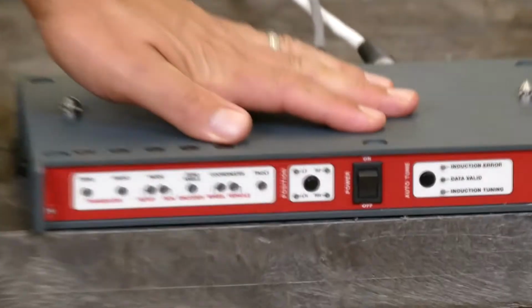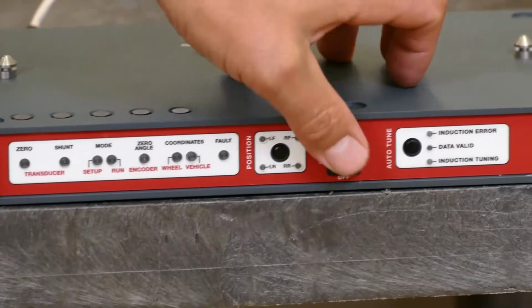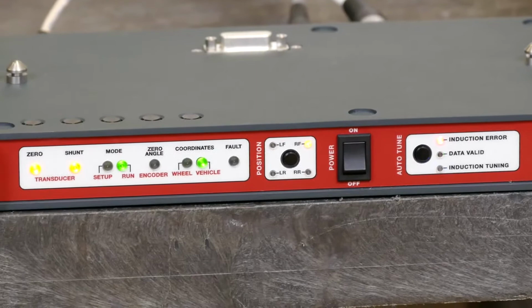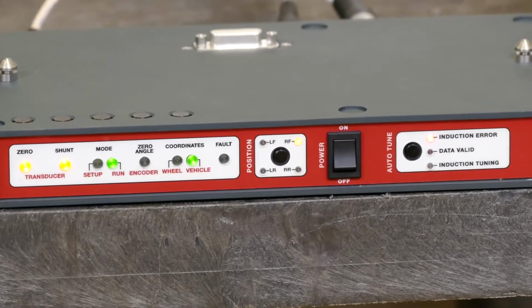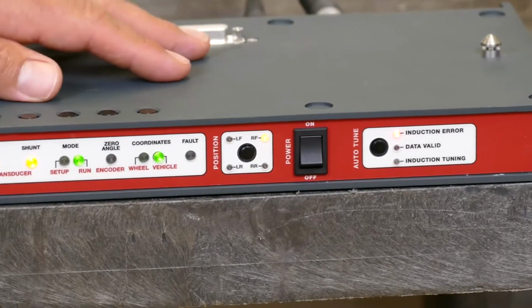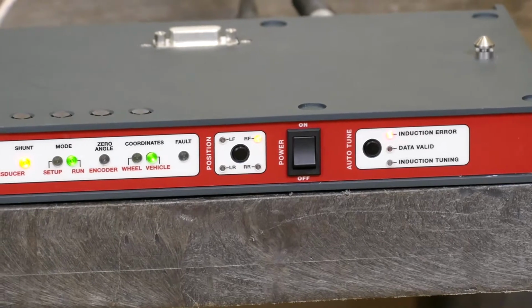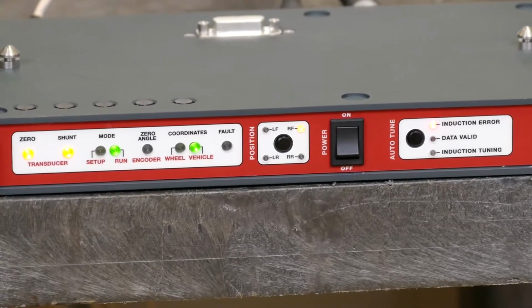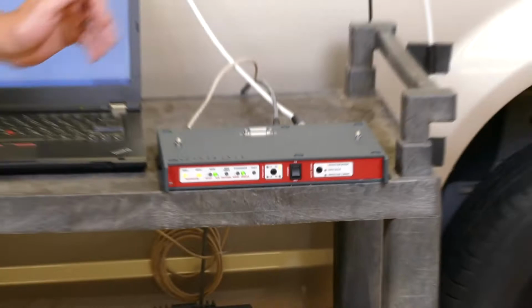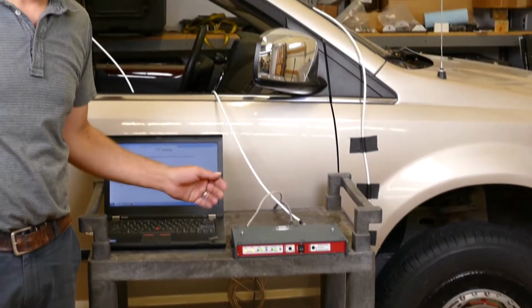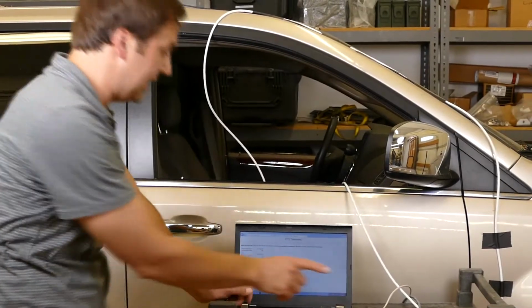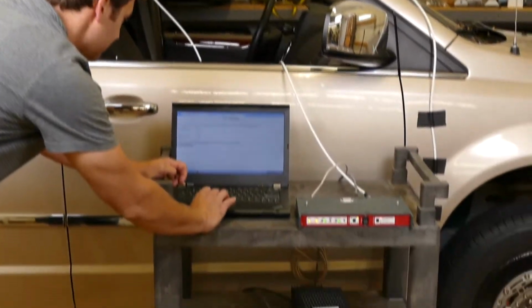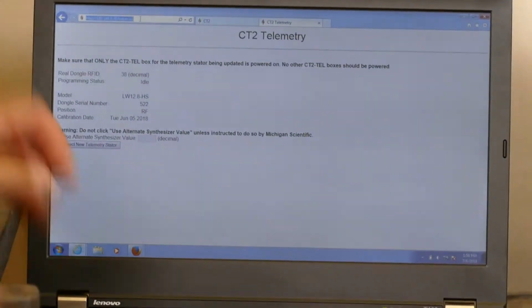We've got power connected to the CT2 box to DC power. We turn on the box. And the first step will be to reprogram the frequency of the telemetry stator. If you've already used them as a matched set or they were delivered in a matched set, then you don't need to do this step. But if you're installing a new stator, then you have to connect to the CT2 web page and connect it to the stator.